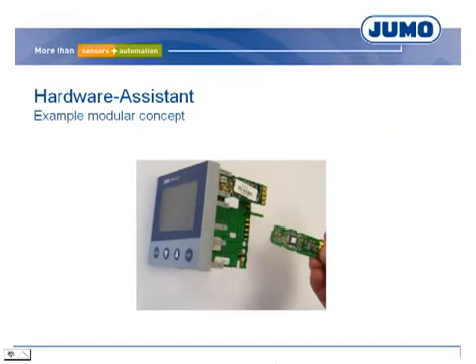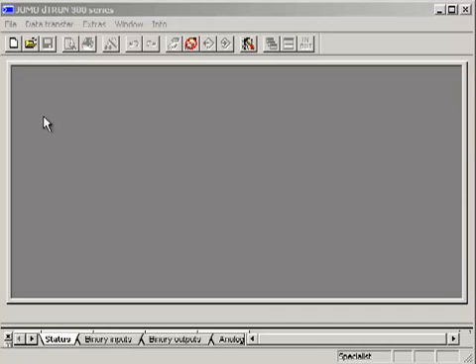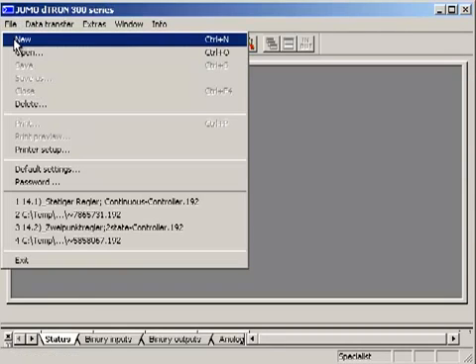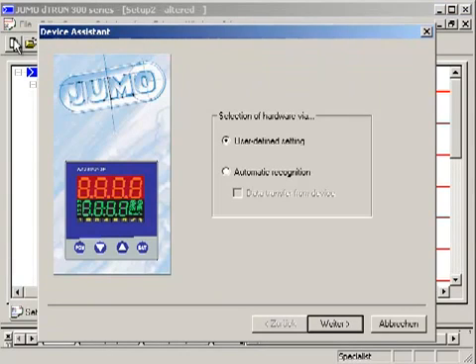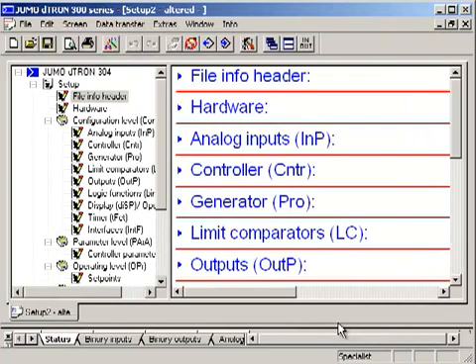Besides a fixed hardware, some JUMO devices possess option slots. This modular concept is used for example at various compact controllers and screen recorders. Furthermore, many JUMO devices are deliverable with different hardware. In these cases the software has to identify the hardware. A new file is created, and normally a connection to the device is possible. It is advisable to use automatic recognition. The hardware is then identified and the configuration can be applied.